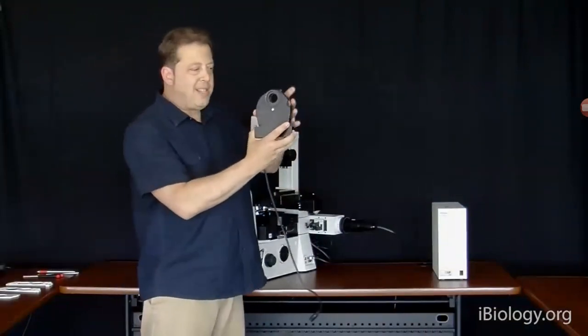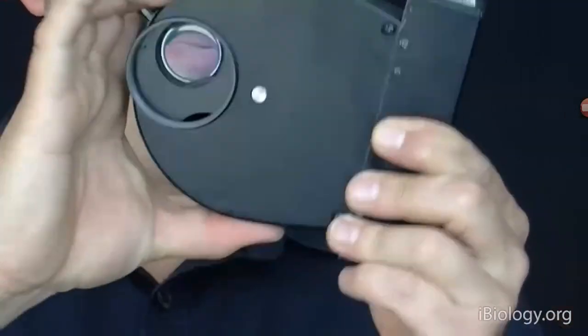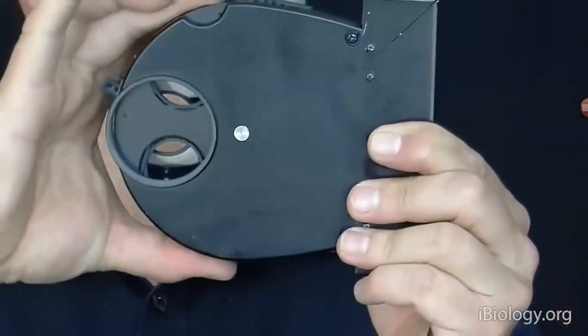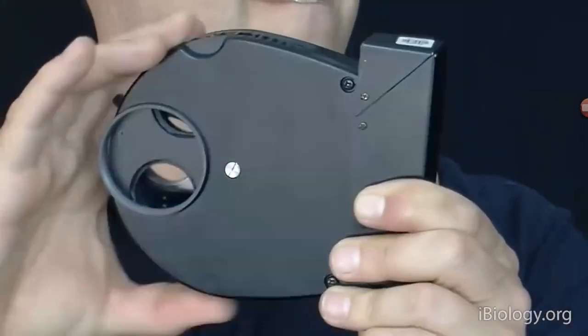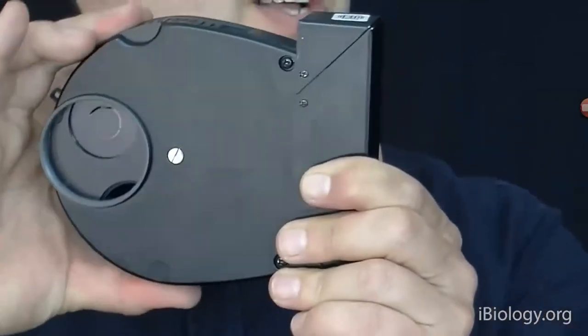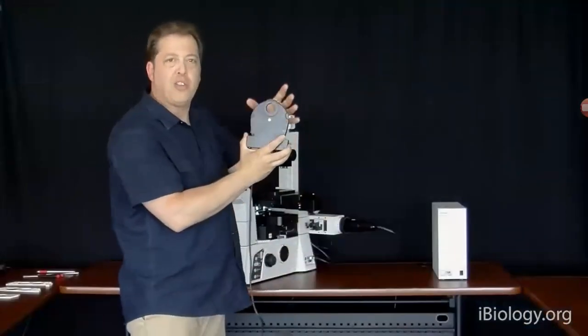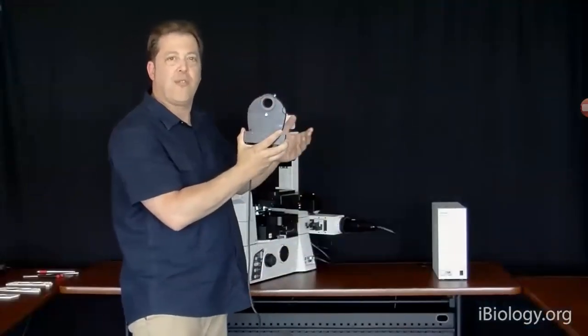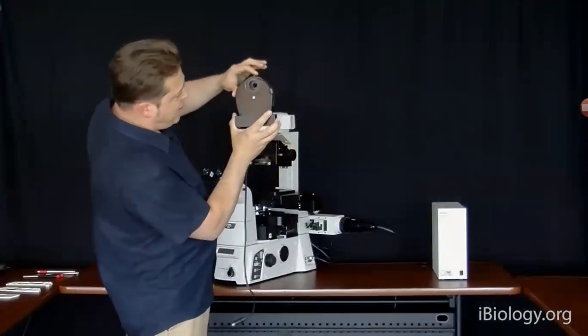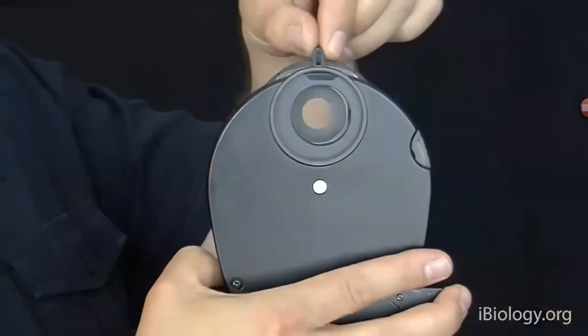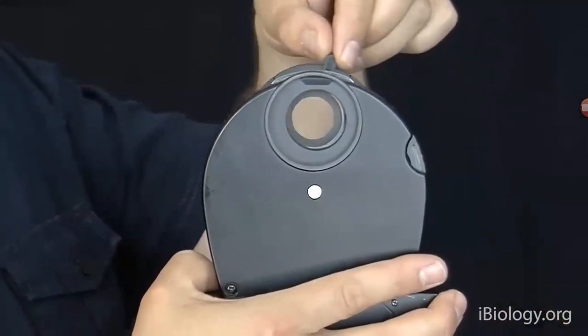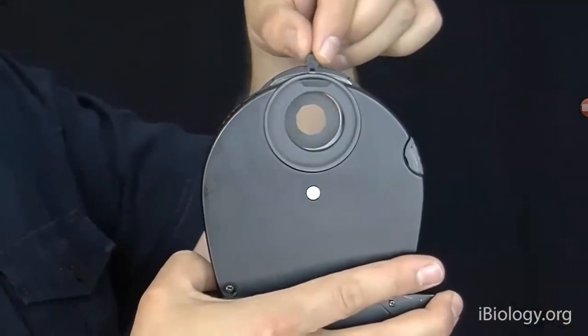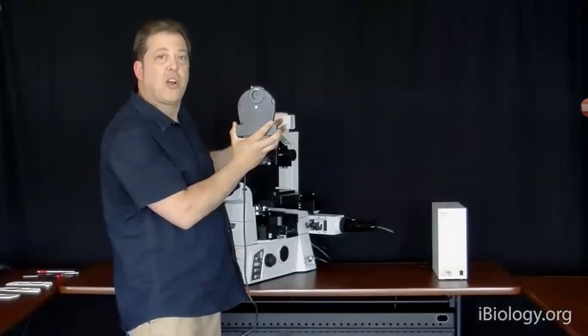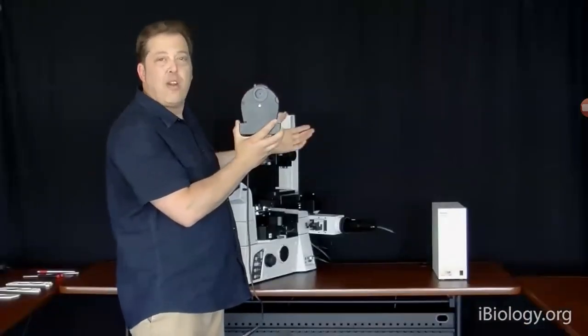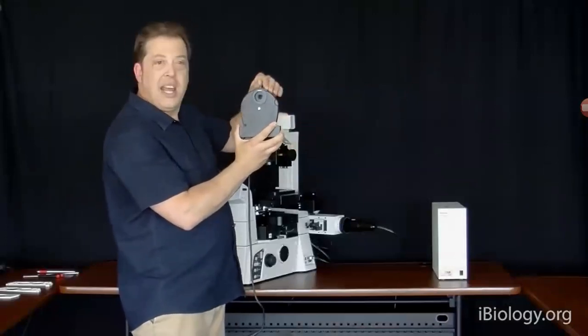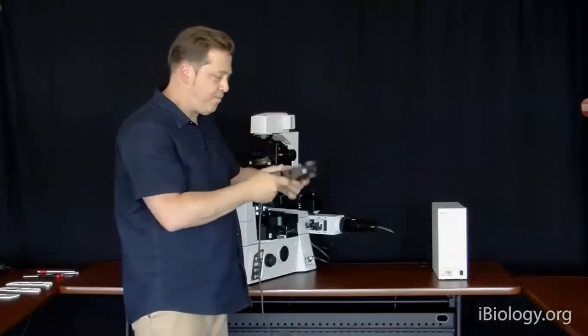So now that we've removed the condensing lens, you can see in here that there's a number of different spots, and we have prisms as well as phase rings in this condensing system. And this is where you would hold all of your modules for differential interference contrast or phase contrast. You can also see that there is another iris in here, and this is an aperture iris. This is the first aperture iris in the microscope. And that's going to actually adjust the cone of illumination and trade off contrast for resolution in transmitted light techniques.